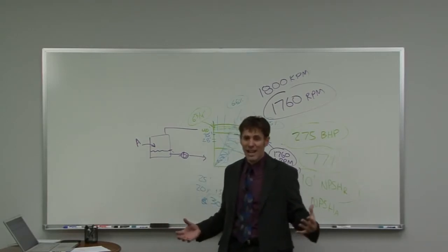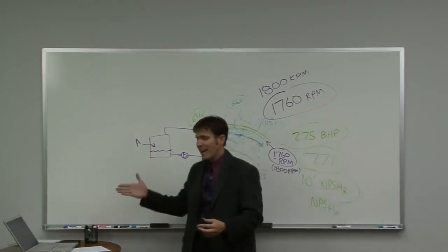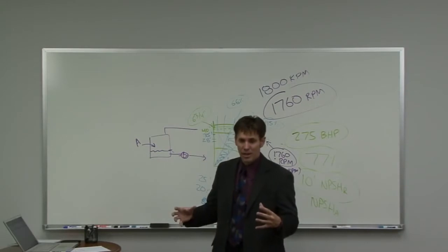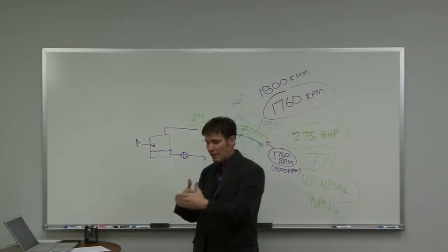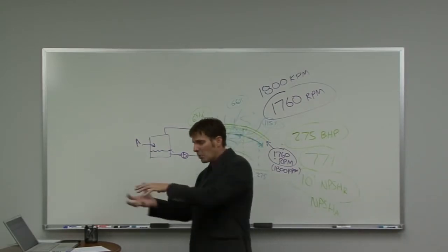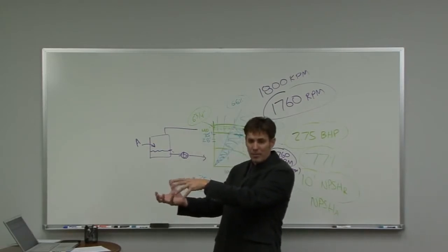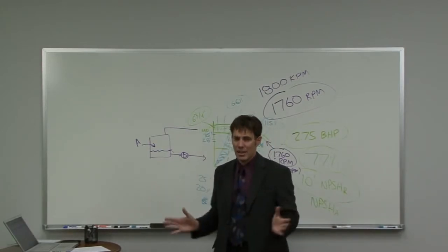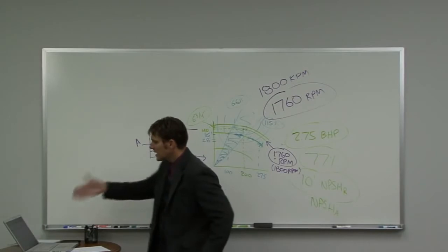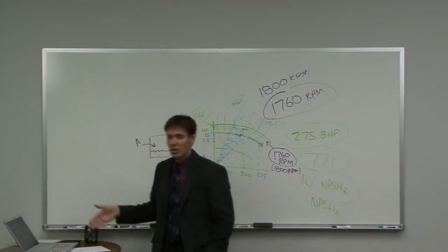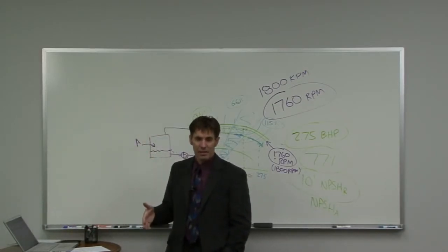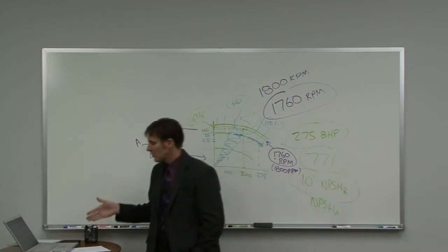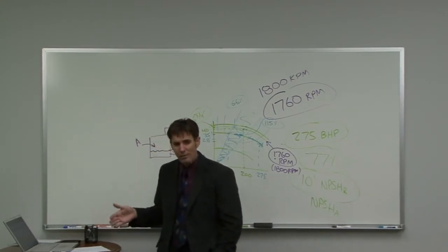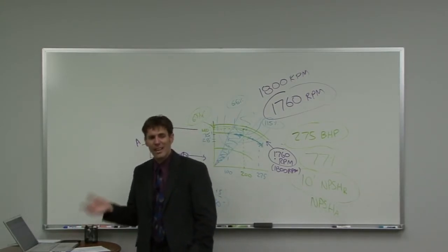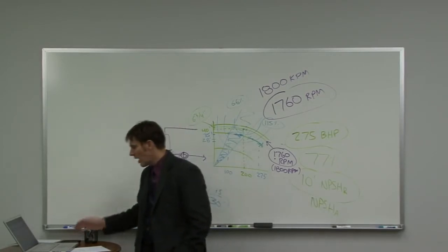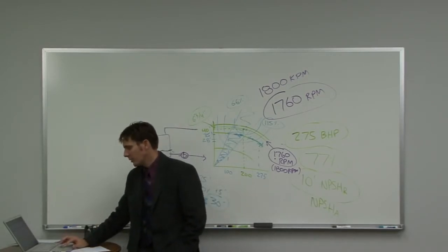I don't want to have to lift that. I don't want to have to deal with that. If I have a split coupled pump, then all I have to do is break the coupling, and I can pull the pump shaft out without even touching that motor. So because of the size of the motor, I would go with a flex coupled pump. If this were a 3 horsepower, 5 horsepower, maybe 7.5 horsepower, then I would consider the closed coupled. So I'm not going to even consider the closed coupled anymore.